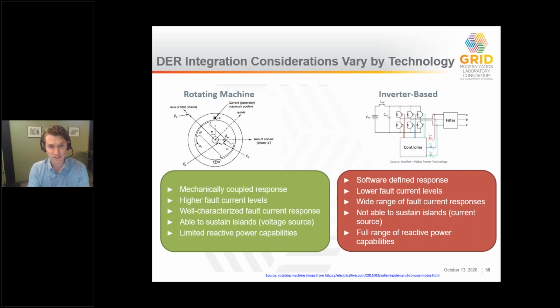By the nature of these devices, these rotating machines have a lot higher fault current. So if we think about protection impacts, and a large amount of energy when a tree drops on the line or a squirrel or whatever causes a fault, that fault current is quite a bit higher than inverters. And these also have a very well-characterized fault current response that's based on the physics of the device. And they can sustain islands. They're actually a voltage source. They can create fundamental voltage on the system that can energize loads, and inverters can follow this fundamental voltage.